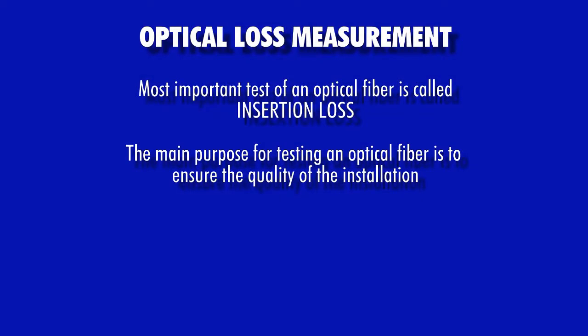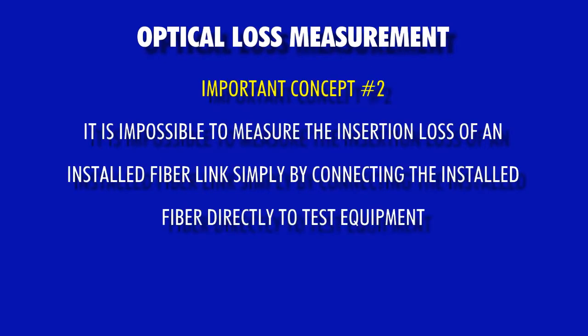The whole purpose of testing an optical fiber link is to measure the insertion loss, or attenuation, of the fiber under test. Optical loss measurement is important because it is an indication of the quality of the installed fiber link. Which brings us to important concept number 2. It is impossible to measure the insertion loss of an installed fiber link simply by connecting the installed fiber link directly to test equipment. Here's why.